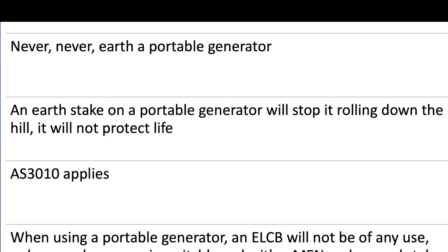Another thing that I think we come across quite regularly when we go portable is portable generators, and it's always been a bit of a bugbear for me when it says, oh, we should put an earth stake in that thing. You never, ever, ever earth a portable generator, because the active and neutral, the neutral is not connected to the case. So the neutral pin, the right-hand pin in the three-pin connector, is never connected to the earth because it can float up and down. I love this quote: an earth stake in a portable generator will stop it rolling down the hill. It won't protect you, all right, without the proper protection systems. To do it properly, you need to have a switchboard and an earth stake separate to the generator. That's the right way to do it.